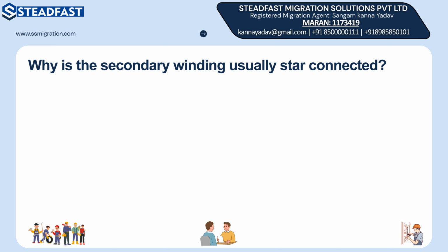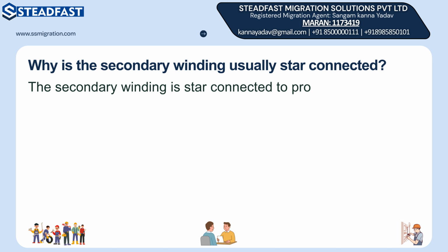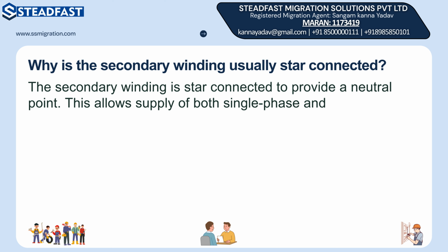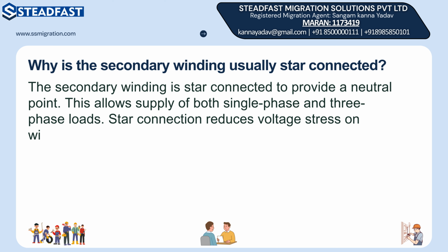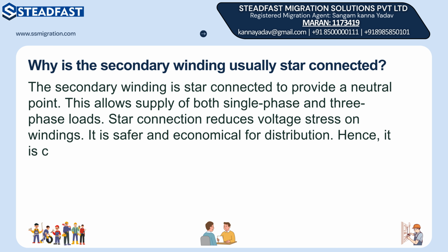In local distribution transformers, which connection is in primary and which in secondary? In local distribution, the primary winding is connected in delta. The secondary winding is connected in star. Delta reduces insulation requirements on the high voltage side. Star provides neutral for household supply. This combination is standard in distribution.